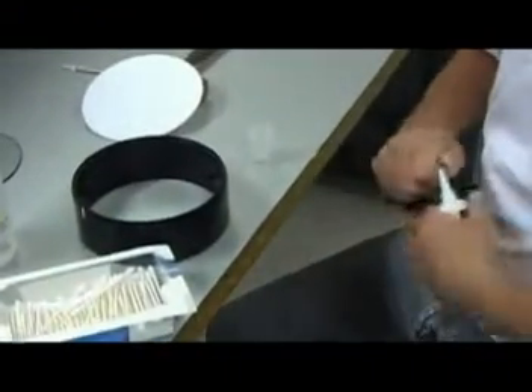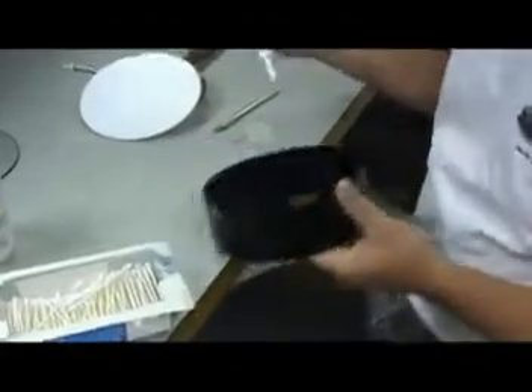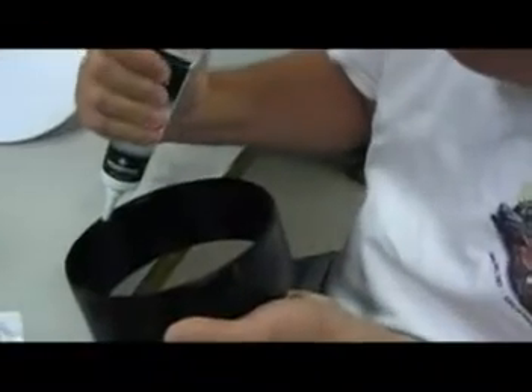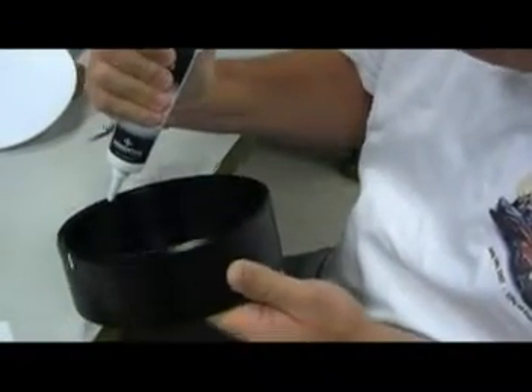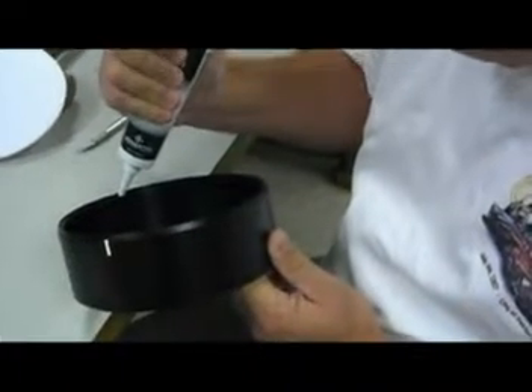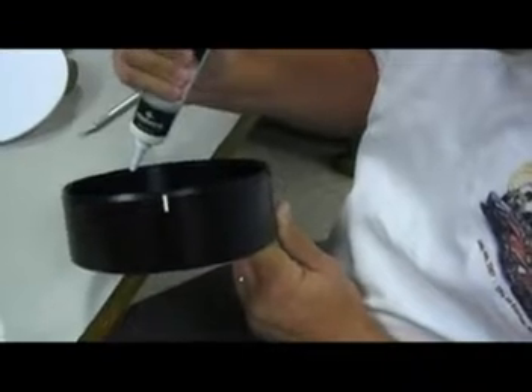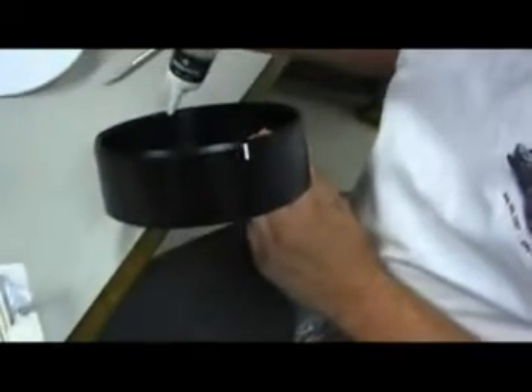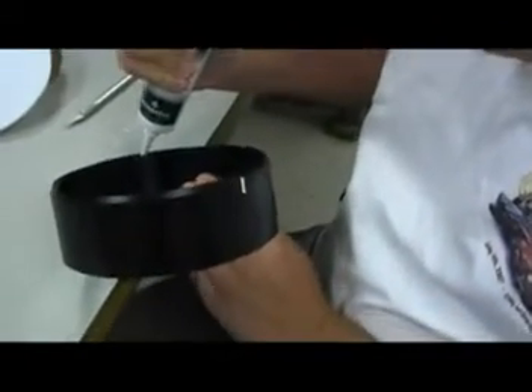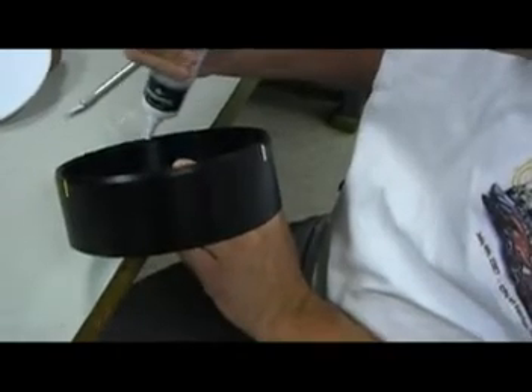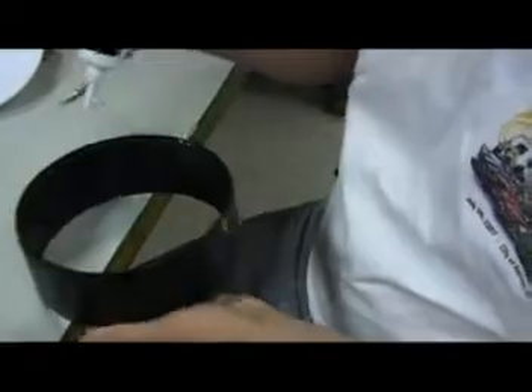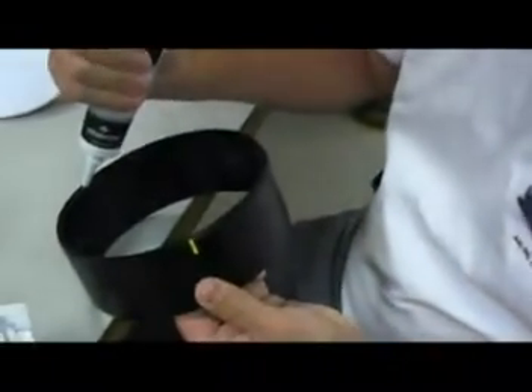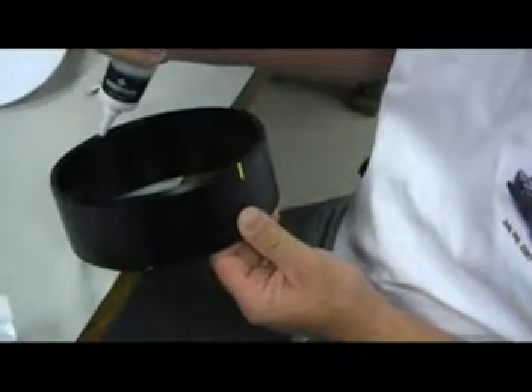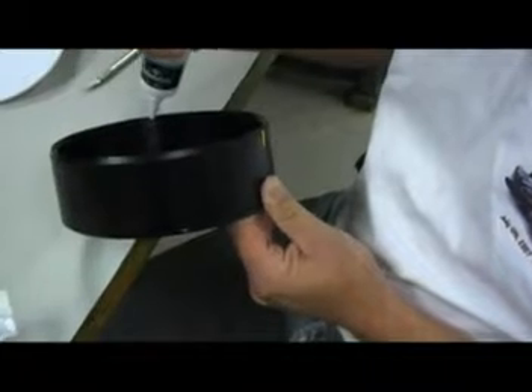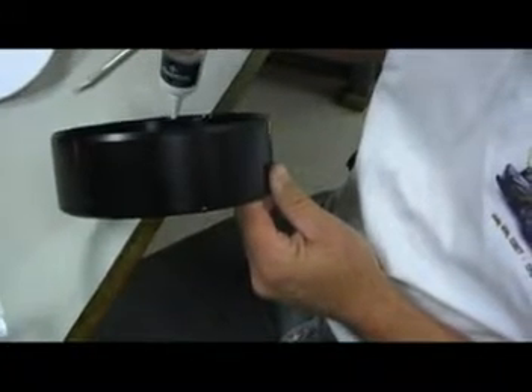We are using black silicone RTV. You can get it in these small tubes. What we're going to want to do is put a fairly thick bead in that entire groove, making sure that there are no voids or no air bubbles. We've got to be careful that when we get around to where we started putting the RTV on, where the bead joins up again, we have complete coverage. The idea here isn't to be neat at this point. The idea right now is to make sure that we completely fill that groove where the polycarbonate disc is going to sit.